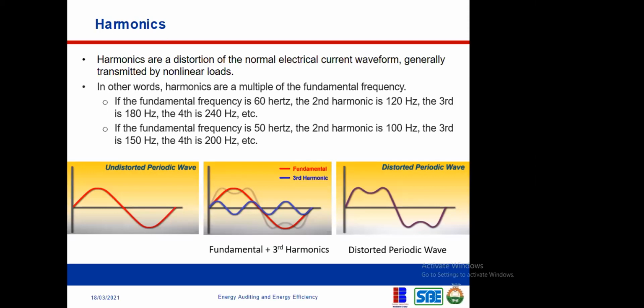When you combine that third harmonic with the fundamental wave you should have, you get the third image—the distorted periodic wave. This was the original electrical wave, and it has undergone harmonic transformation; harmonics have affected it, and this is now what we have as the electrical wave, which is wrong. This can cause problems in an electrical system. This is what we call harmonics.